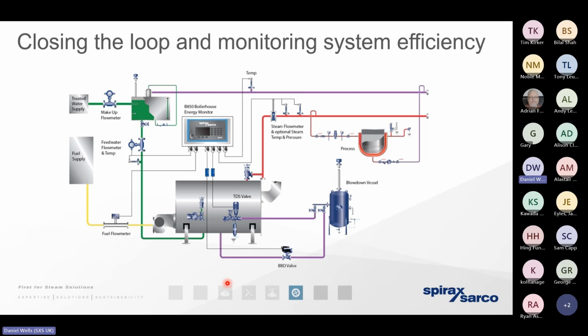If we're not recovering as much condensate as we may like, that could be down to the fact that we've got failing steam traps that are venting steam away, or we've got flash steam emissions that are arising from other sources, or maybe we've got fractured, damaged valves and pipework components.